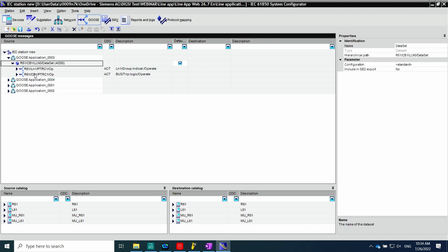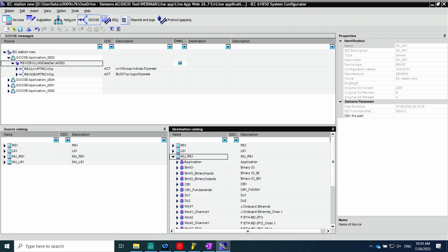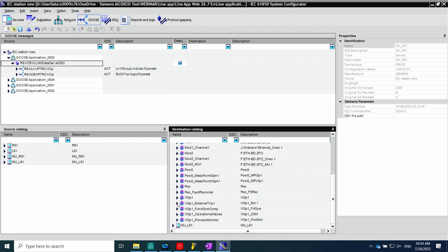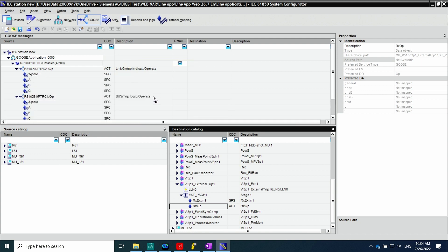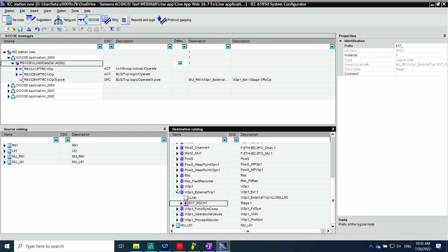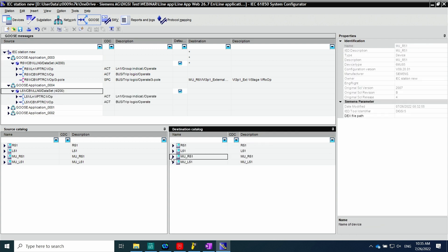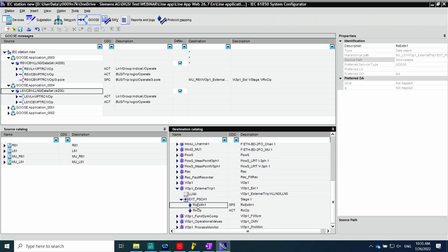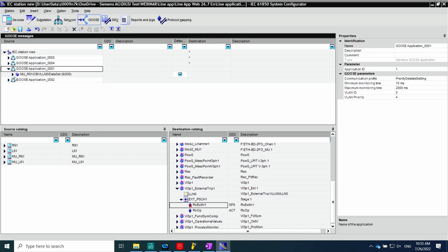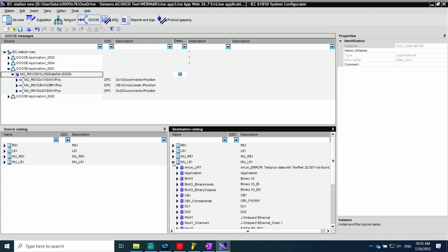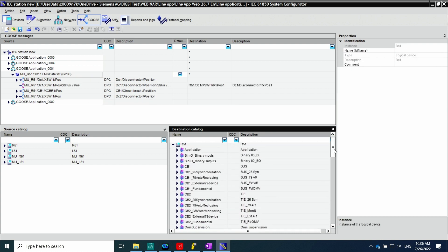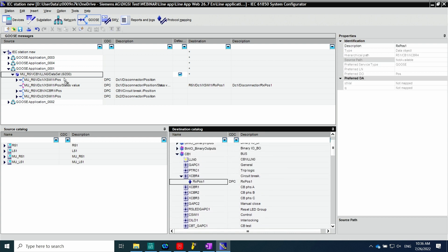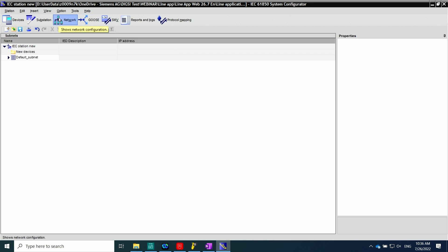To link binary information, the GOOSE menu is used. By clicking on GOOSE, the GOOSE applications are displayed. Here is the information being sent from relay R51 to merging unit R51 — the external trip and voltage and current function group connected with the circuit breaker trip indication coming from the trip logic. The same is done for L51. Signals sent from the merging unit to the relay include the positions of the disconnector and circuit breaker. Looking in relay R51 and checking the disconnector, when the logical node is found, the position is connected. The same is done for the circuit breaker.